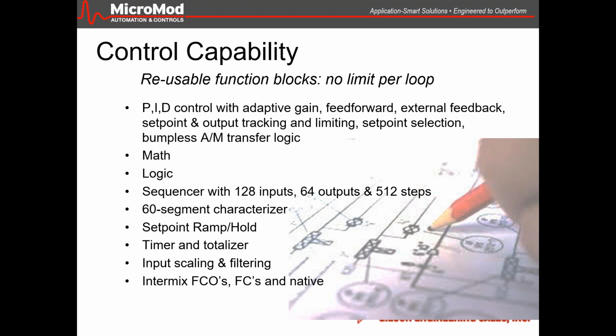Here's where we're different from the 352 and 353s. In the 352, people got used to FCOs -- pre-configured canned algorithms they could just load in, put in their spans, ranges, alarms, and go. Very quick and easy. Or they could mix in function codes. The 353 had its own set of FCOs and function codes, but the problem was a lack of ability to mix the two in some cases.